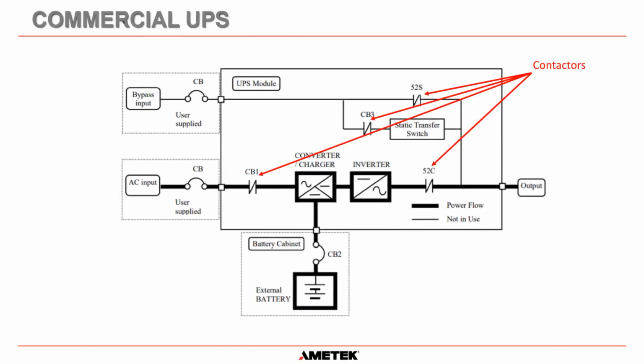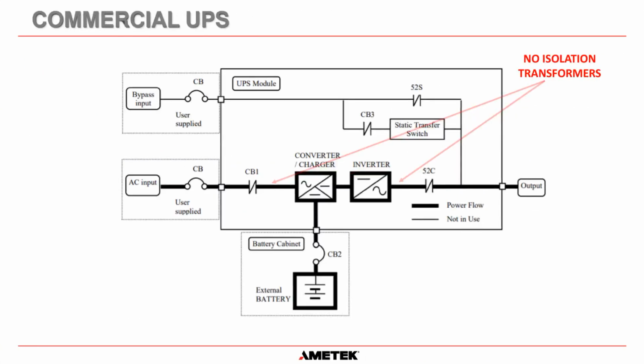So remember, these are contactors. This is actually a circuit breaker. I shouldn't have labeled that as a contactor. They are circuit breakers in this system here. Okay. But the important thing to remember is there's no isolation transformer here in a commercial UPS and no isolation transformer there. And that's important because that gives you galvanic isolation. It gives you isolation between the two power sources.